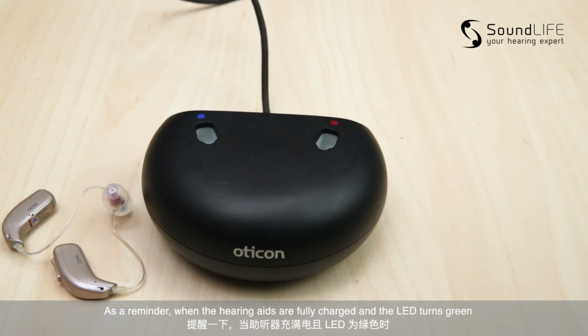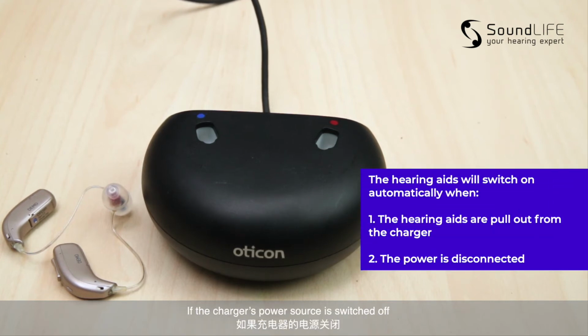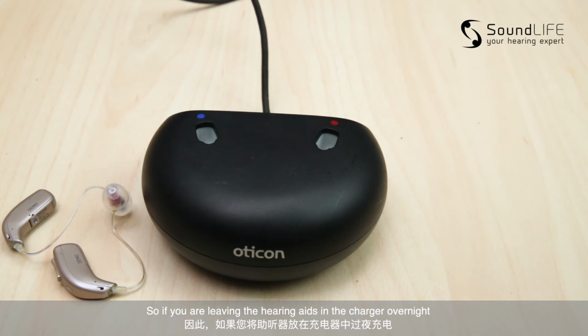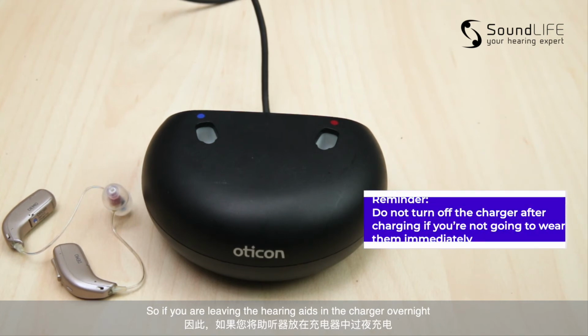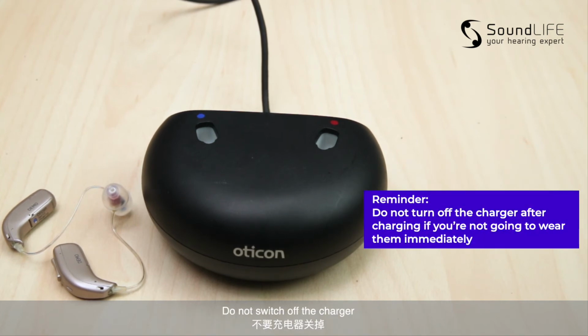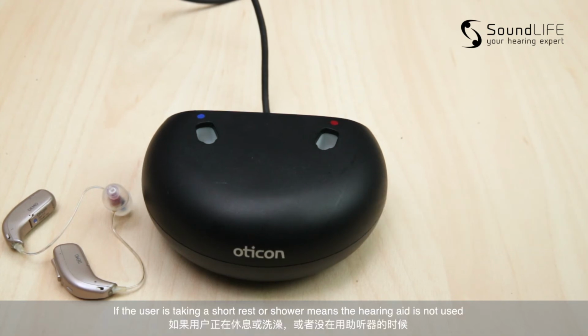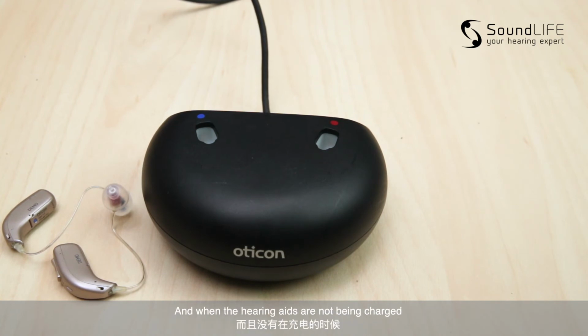So, as a reminder here, when the hearing aid is fully charged and the LED turns green, if the charger's power source is switched off, the hearing aids turns on automatically and it starts draining the battery. So, if you are leaving the hearing aids in the charger overnight, do not switch off the charger. If the user is taking a short rest or shower, means the hearing aids is not used and the charging process is also not done, please switch off the hearing aids manually so that the battery is saved.